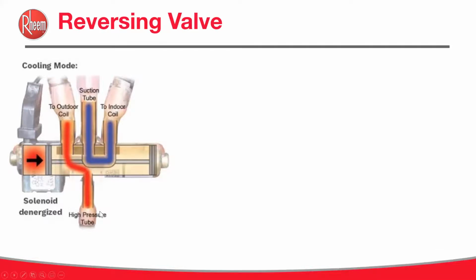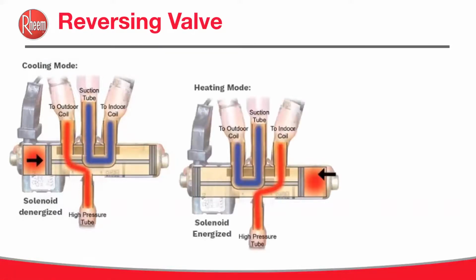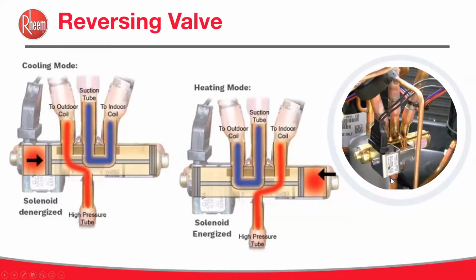So in this situation, as you see here, the bottom tube is your high pressure tube. It's always high pressure, and it redirects discharge gases to the outdoor unit. We have your suction tube. Again, the center tube is your true suction. It is always suction. And it brings vapors, not to the indoor coil, but from the indoor coil back to your compressor. So what happens when we go into heating mode? All that happens is that we now redirect the high pressure, high temperature gas to the indoor coil. And we now suck vapors from the outdoor coil back through the true suction line to the compressor. So that's all the difference there is, redirecting where we put the hot and the cold. This is an actual view of one. So again, you can see what it looks like.